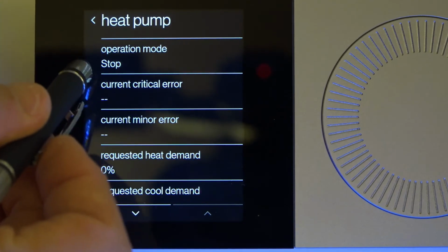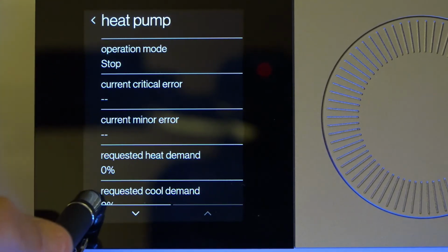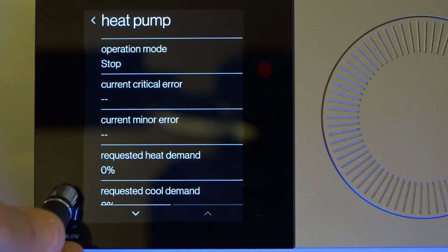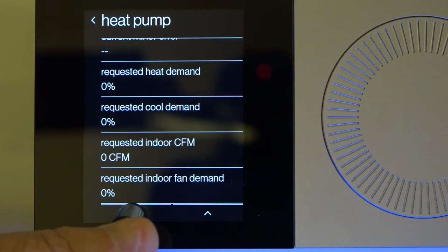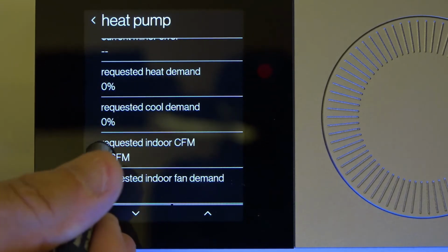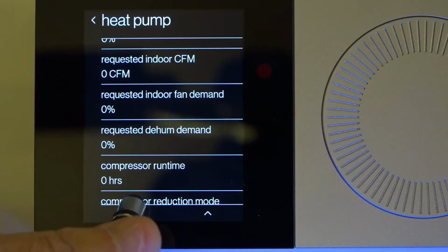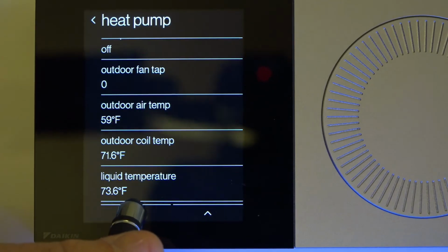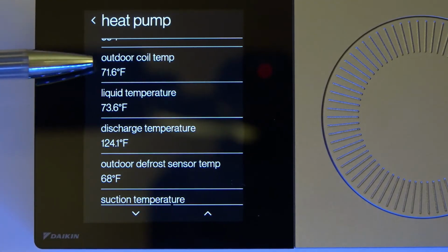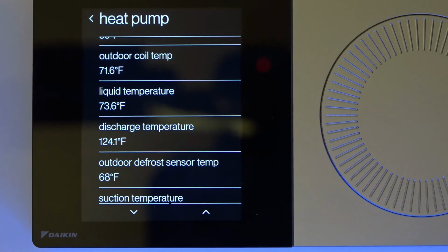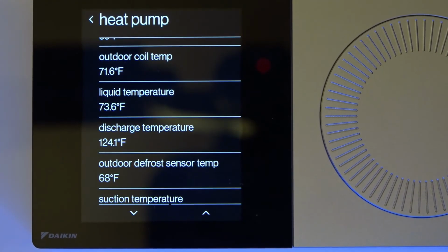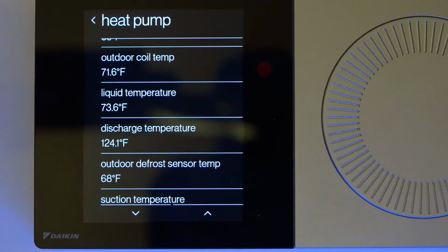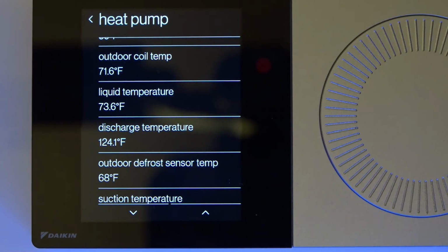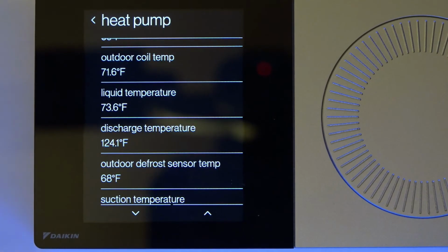It tells me what mode we're in. Do we have any critical or minor errors here? It'll tell me the requested demand for the compressor. And then CFM, it gives me a bunch of information. I'll get down here towards the bottom, and it'll give me some of the thermistor values that are on the liquid line, suction line, discharge pipeline, outdoor temperature, items like that. So it's got a bunch of thermistors monitoring the refrigerant temperature all through the system, so I'll be able to see all of these directly from the status screen here.